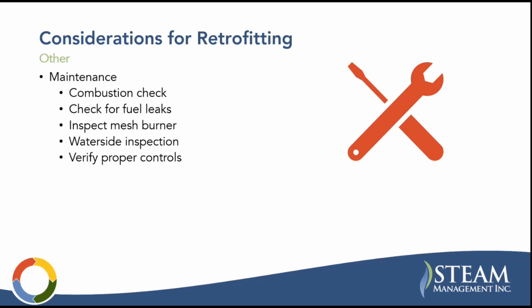Maintenance. So one thing to note here, these things come in kind of fancier packaging than traditional boilers. It sometimes makes it feel like it's more of a refrigerator or a residential furnace or something where you're not typically popping the cover yourself and doing a lot of maintenance. So don't fall into that trap. These things do require maintenance. You've got to do combustion checks, checking for fuel leaks, inspecting that mesh burner, water side inspections, and verifying that your controls are operating correctly.